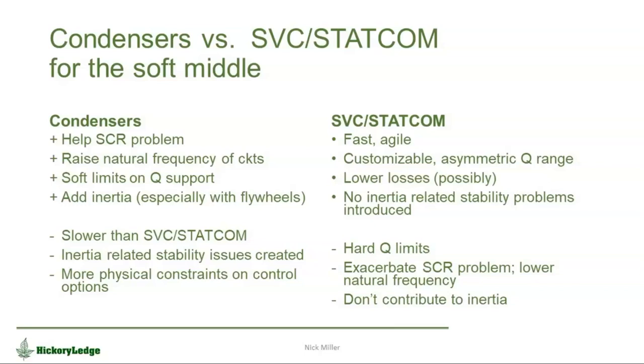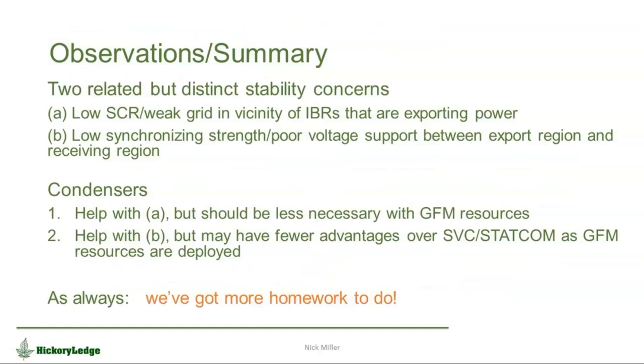So in summary, we've got two classes of stability problems that are related but not identical. One is keeping the sending end stiff enough by adding condensers, and the other is to keep the soft middle supported enough to manage export. Those are not the same problem, although they're related. The first problem, the sending end, should be less necessary with grid forming resources.